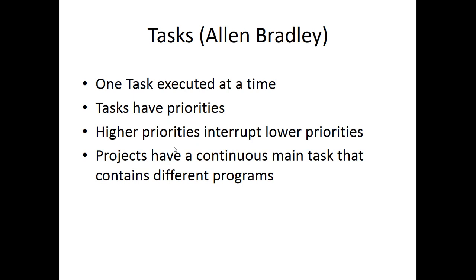We talked about programs and tasks having priorities. Higher priorities interrupt lower priorities. Usually the continuous tasks are low priority, and any kind of intermittent task stops that from running, and it would run the higher priority tasks. Okay.